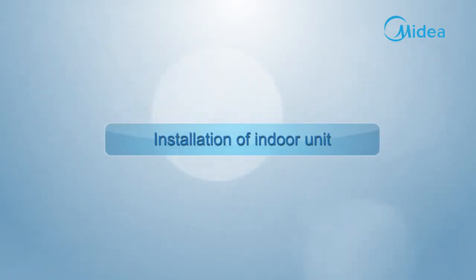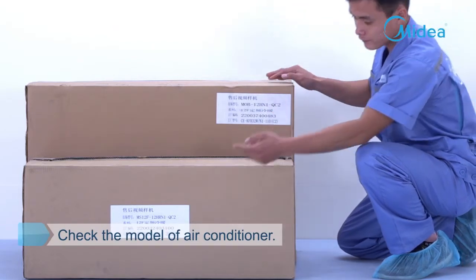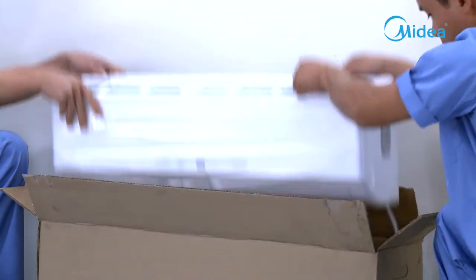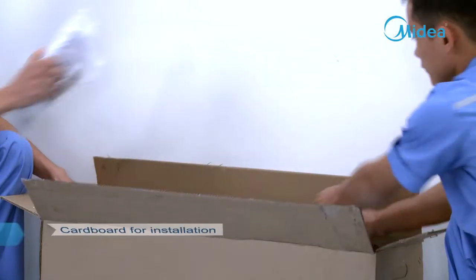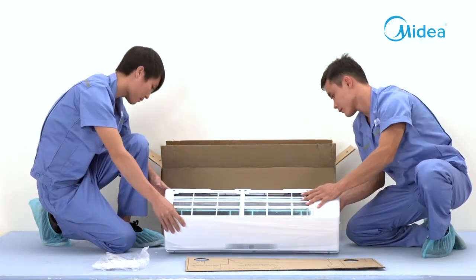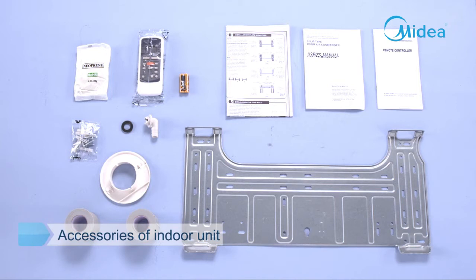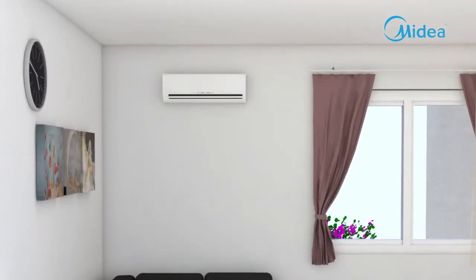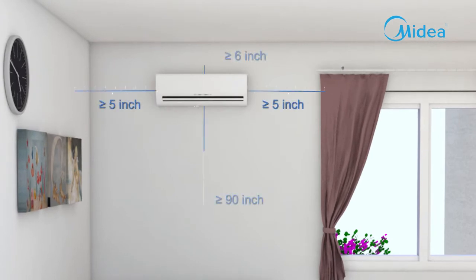Installation of indoor unit. Confirm whether the indoor unit matches the outdoor unit according to the product model. Unpack the packaging box, take out the indoor unit, and examine whether there is any scratch, deformation, or other defects on the panel. Take out the cardboard for installation and check whether all accessories are complete. Space requirements: the right and left sides of the indoor unit should be more than 5 inches from the wall, the upper side more than 6 inches from the ceiling, and the lower side more than 90 inches from the ground.